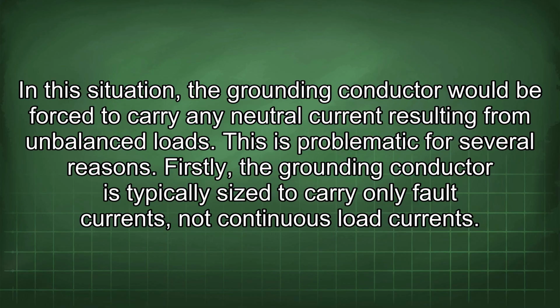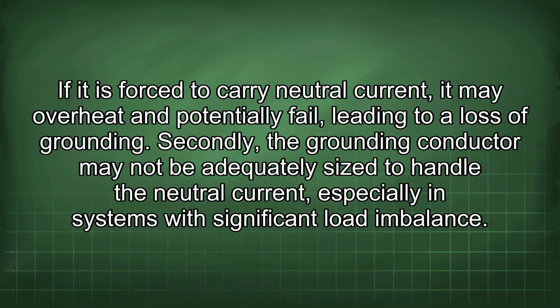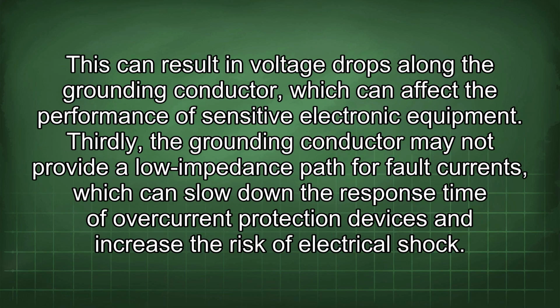Firstly, the grounding conductor is typically sized to carry only fault currents, not continuous load currents. If it is forced to carry neutral current, it may overheat and potentially fail, leading to a loss of grounding. Secondly, the grounding conductor may not be adequately sized to handle the neutral current, especially in systems with significant load imbalance. This can result in voltage drops along the grounding conductor, which can affect the performance of sensitive electronic equipment.